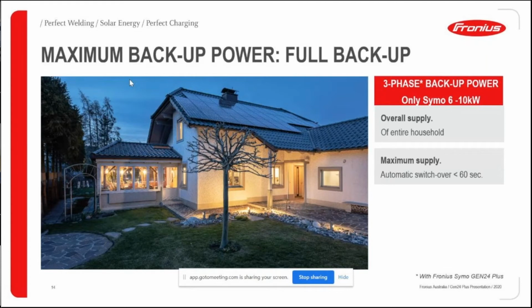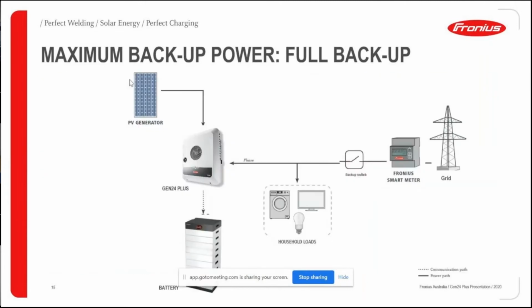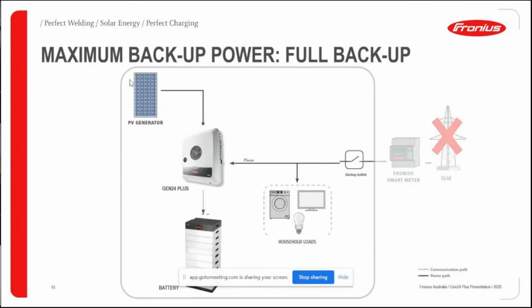There is a switchover time of up to 60 seconds from when the grid goes down before the backup kicks in. It also supplies single-phase load, so it can be unbalanced between the phases as well. I've just got a slide here that shows what happens when the grid goes down. You will require a separate backup switch box. There are some components you need that aren't supplied by Fronius, which is a contactor and a 12-volt relay, to disconnect the Gen24 from the grid. Once it's disconnected, you're in backup mode and you're able to supply power to the loads and also charge the battery at the same time.